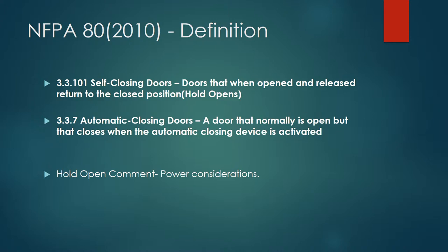Self-closing doors are often on corridors and egresses that are smoke partitions or smoke barriers. People who occupy those spaces, particularly in converted office areas, don't want the doors closed and will block them open. One option is to convert to an automatic closing door that releases in case of fire, or install a hold-open device — both are better than having people block doors with wedges or ties.